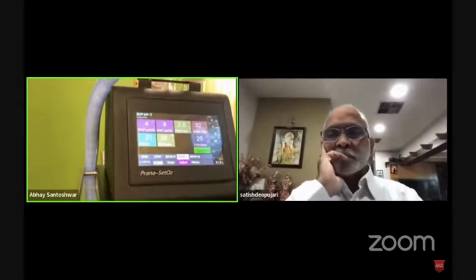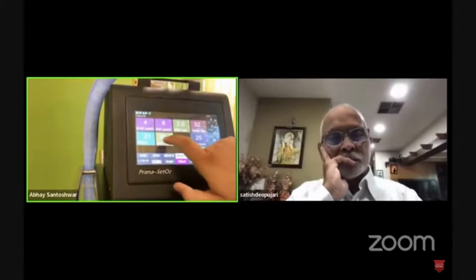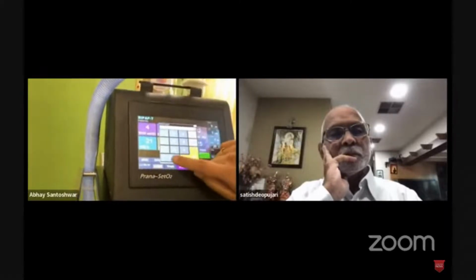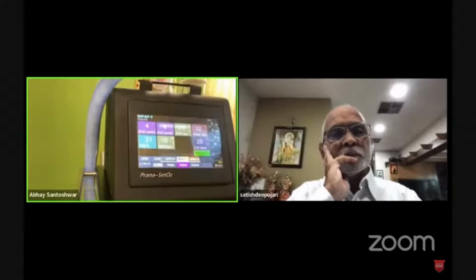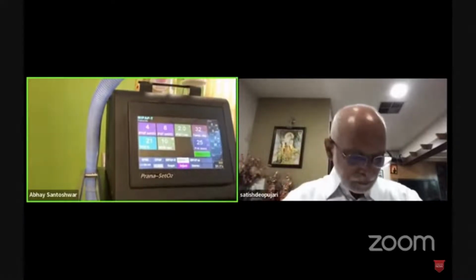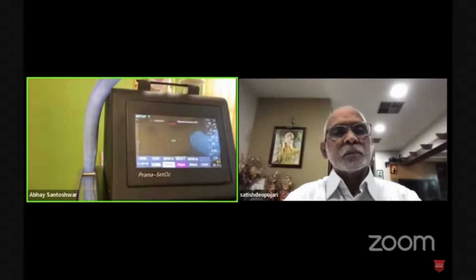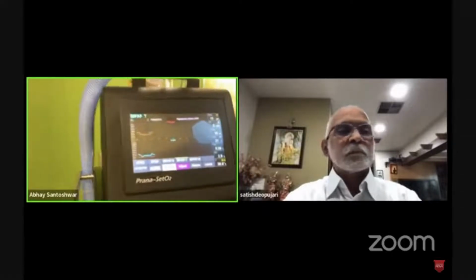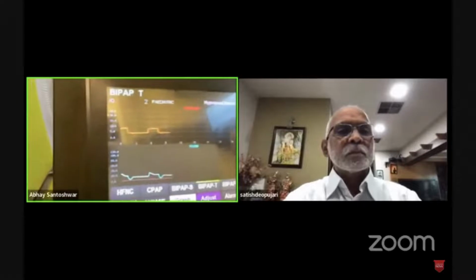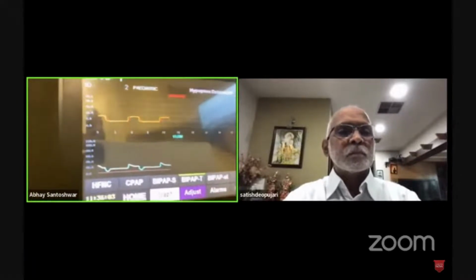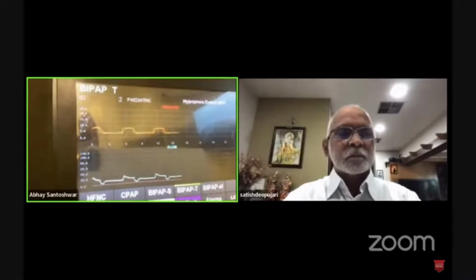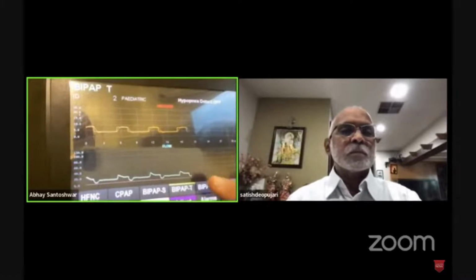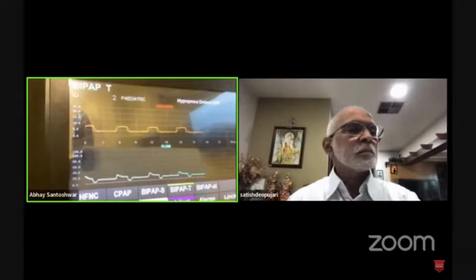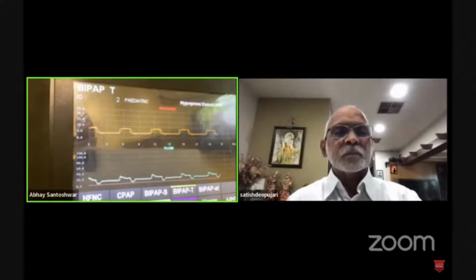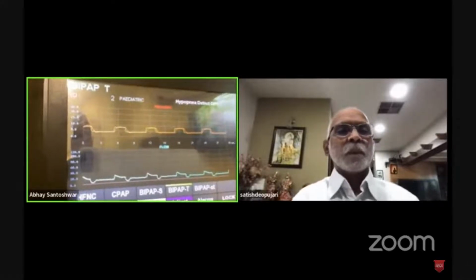So I would ask my colleague to please change the rate to 10 so that we have the scenario where we will have 2 seconds for inhalation, IPAP time, and 4 seconds for EPAP time. Please start. So this is where I think the beauty of verified waveform comes in. We call it verified waveforms. The pressures are being delivered the way that you want, but due to the compliance of the lungs, and since we have also changed the peak flow times, you are able to get these kinds of waveforms.